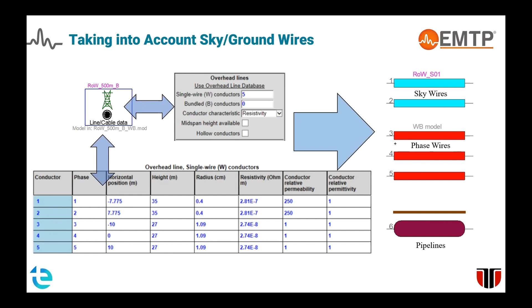For our first evaluation of the induced voltages and currents, we considered an ideal case when the sky wires are interconnected from one end to the other, and grounded only at the ends of the common distribution corridor. In this case, we ignore the presence of the towers and the metallic connection between the sky ground wires and the metallic structures of the power line towers.